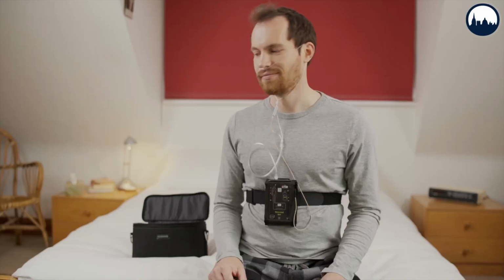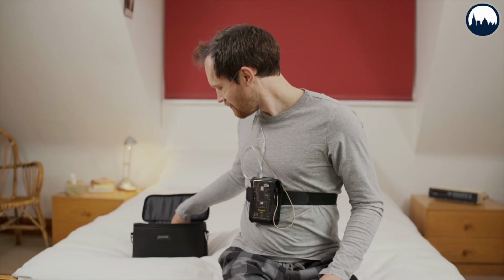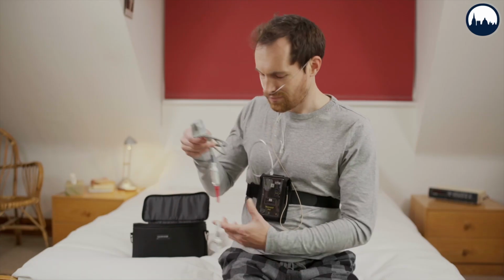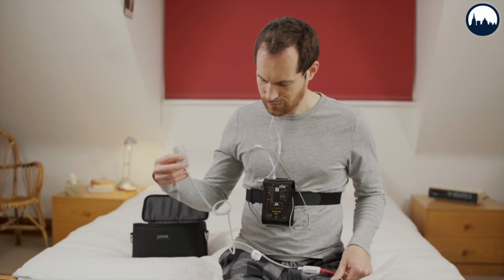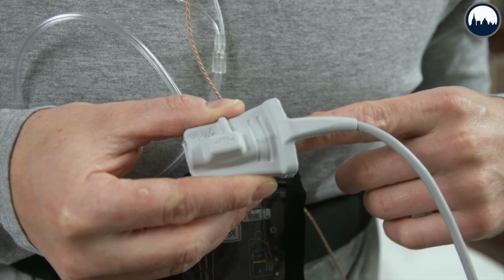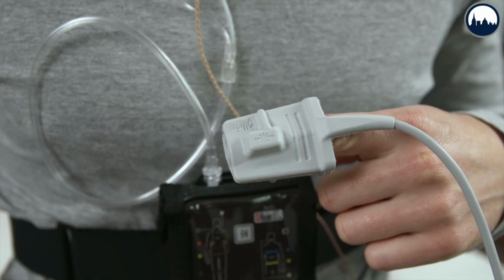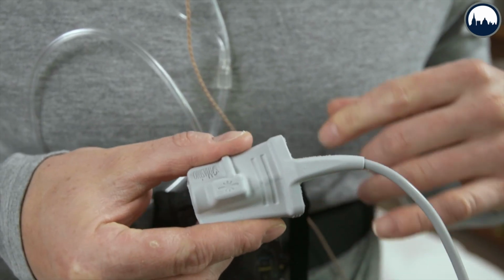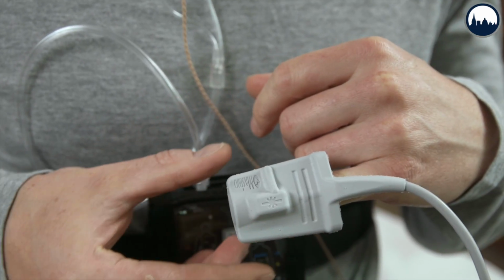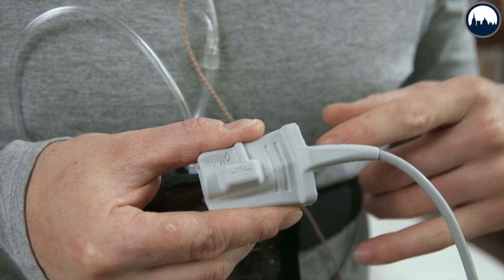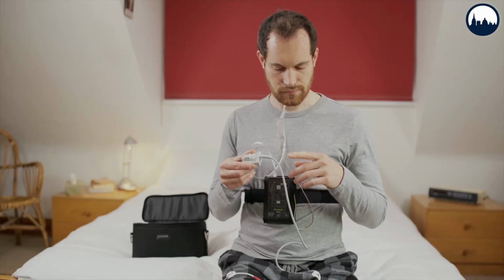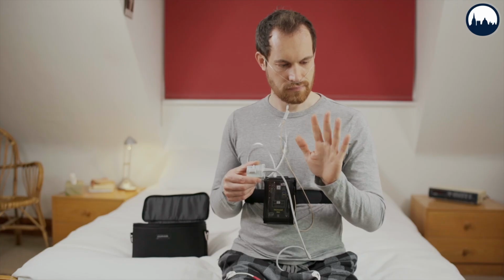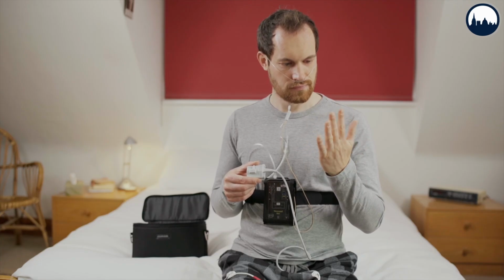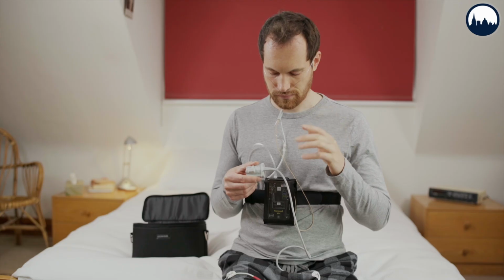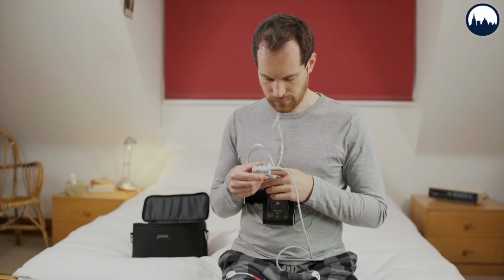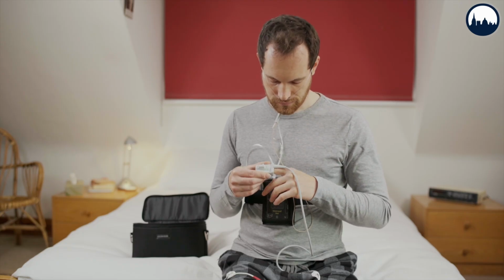Next, we'll fit the oximeter sensor. Slide the left index finger into the oximeter probe so that it is comfortable. If it feels too tight, use a smaller finger. Be sure to remove any foreign materials from the finger, including nail extensions and nail polish. Once you have removed any foreign material and the sensor is comfortably fitted, secure it with some tape around the cable. Do not put tape around the probe body.